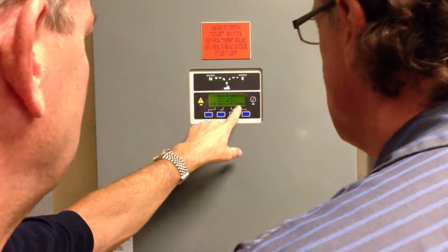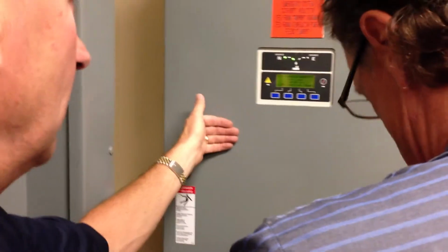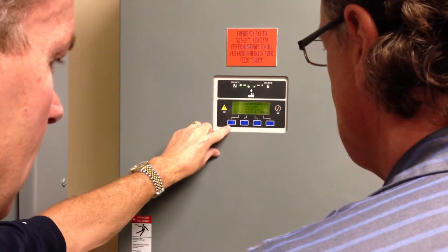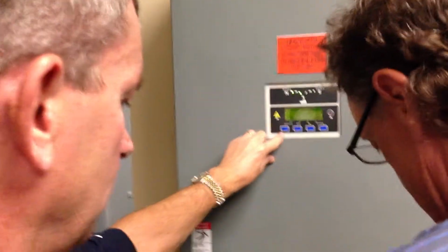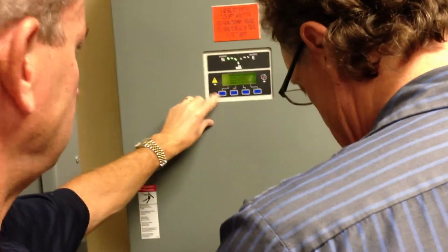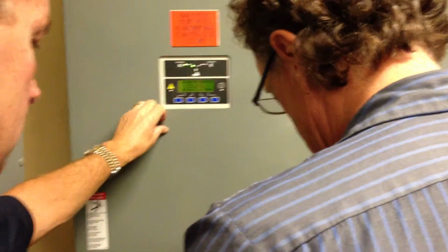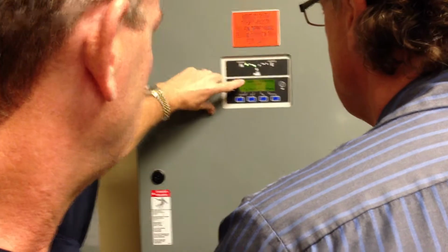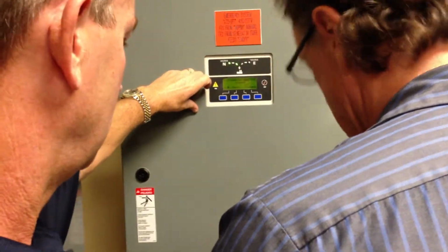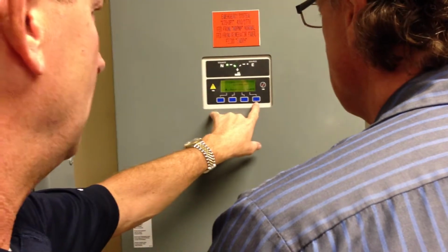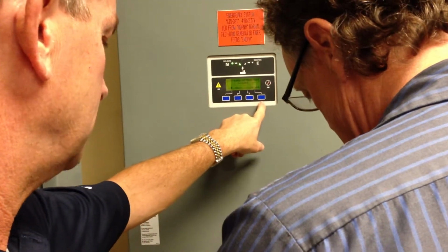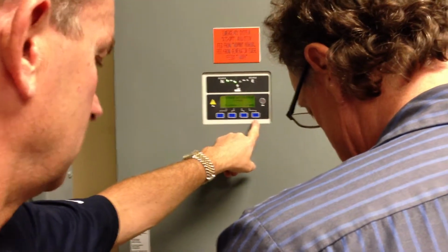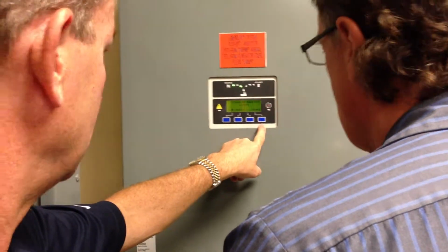If you push it right now, it defaults to an unloaded test, and you want to go to a loaded test. So you want to hit this arrow down button right here. Then hit first button. Okay, now it's telling you type of test, it's loaded. You can do one of two things. What I do now is just hit the start button, and you've got your test. Just hit the fourth button, where it says start the test. So now you're good.